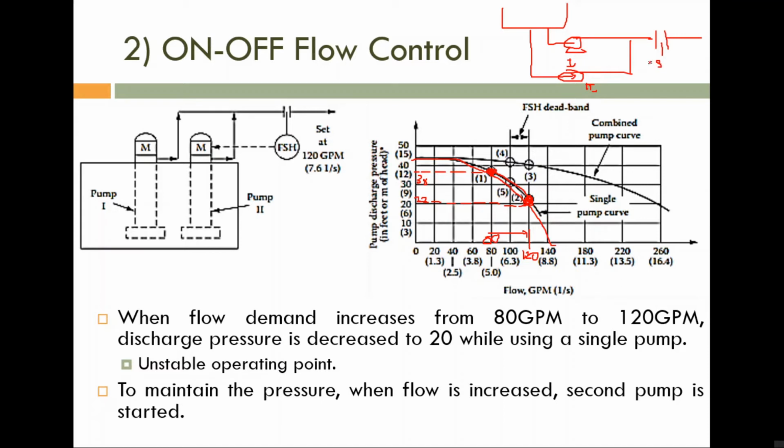If the flow rate is greater than or equal to 120 GPM, which is the set point, then the second pump is also started.